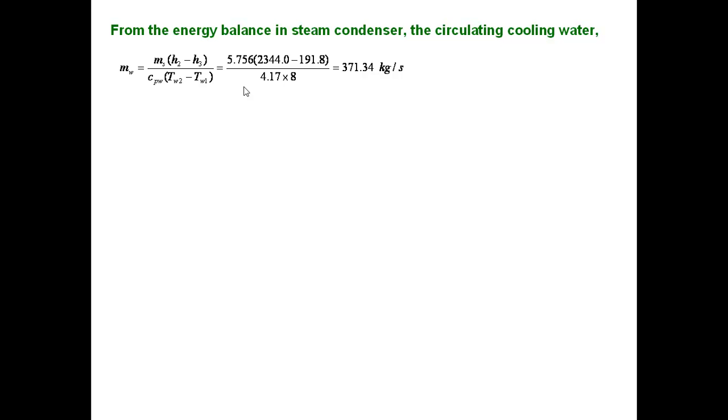After simplification, it is coming as 371.34 kg per second. This much amount of circulating cooling water is required in the condenser to condense the steam into the saturated liquid conditions.